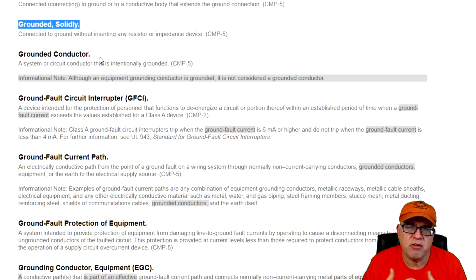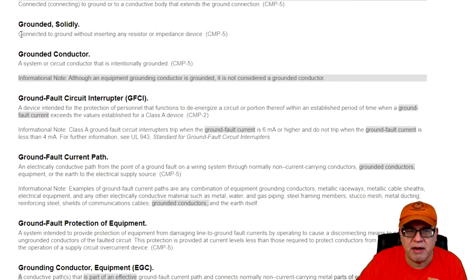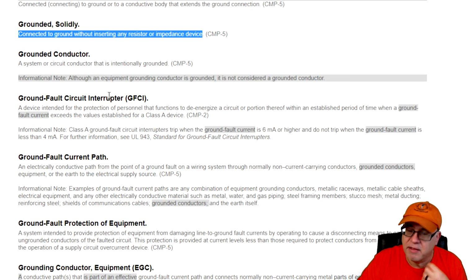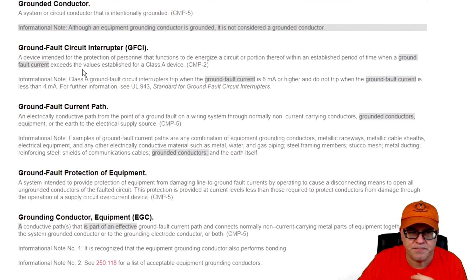Now, we have occasions where we put high resistance resistors in there or even impedance devices. That means it's not solidly grounded, but it's replicating the ground reference, and that's what the resistance device is in there for. But it's not really solidly grounded, so that's what this is telling you. To be a solidly grounded system, I can't have anything in there that could potentially affect that path to ground. So something connected to ground without inserting any resistor or impedance device is considered solidly grounded.